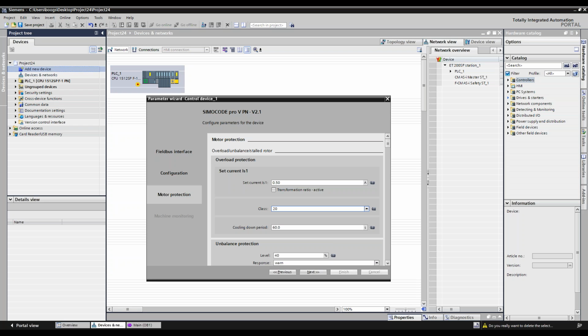The non-solid state overloads were heaters. They were bimetallic metal heaters. It was two dissimilar metals, and as the current flowed through them, they started to heat up. Both of them had different rates of thermal expansion, so one would trip differently, curling away and tripping that motor. But then it needed a cool down period for those heaters to cool off. It would take 300 seconds for them to cool off before the motor could start again. So in here we can simulate a NEMA starter with thermal bimetallic heaters.